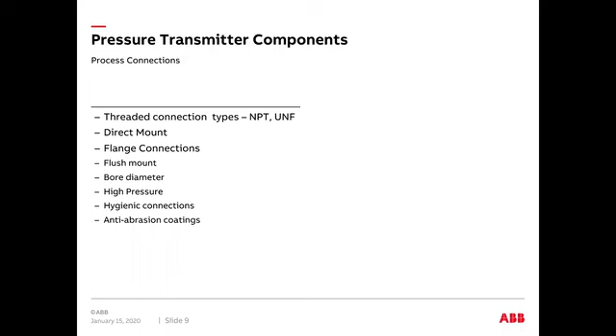Another thing, if you go beyond maybe some of the standard applications, you might need to move to a remote seal. So the remote seal is as pictured there. You're basically taking that pressure reading through a remote seal that is put into the application. Then with a capillary tube, you're running to the actual transducer. With the ABB pressure transmitters, the entire sensor, capillary, and diaphragm seal doesn't have any gaskets or any threads. It's all welded all the way through and tested throughout all those welded connections.